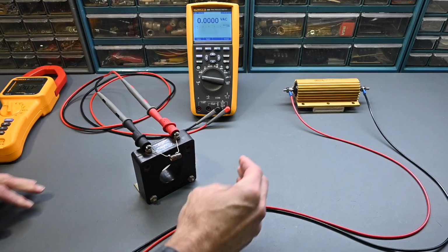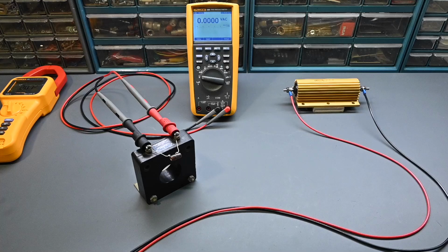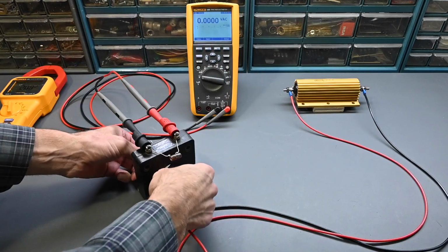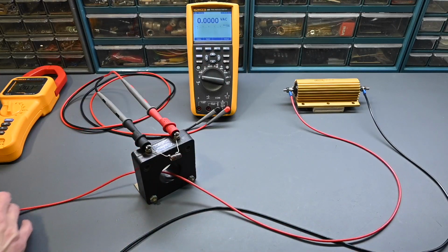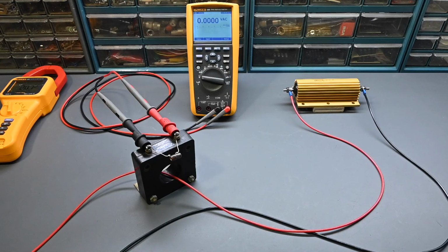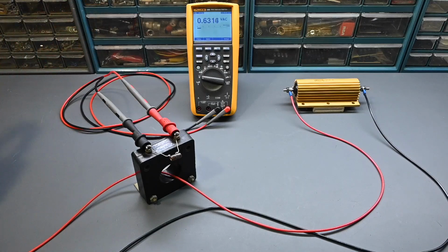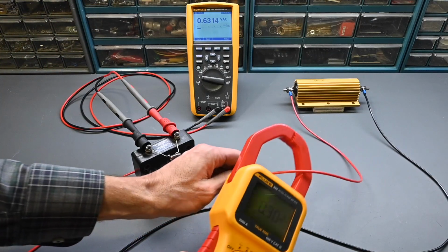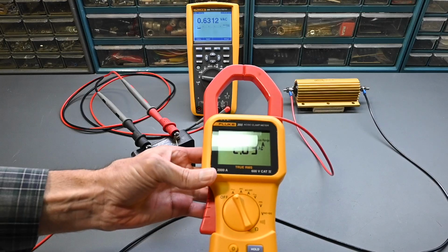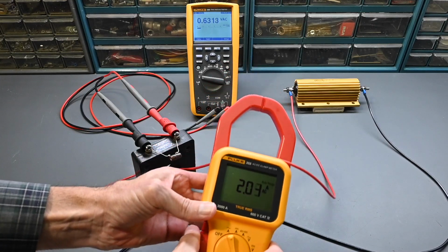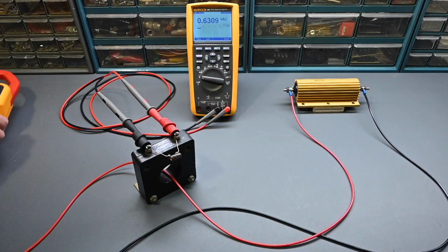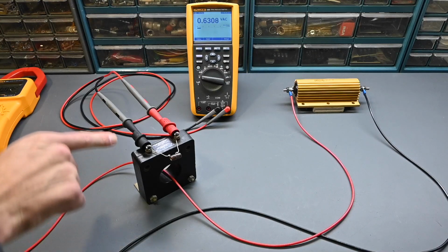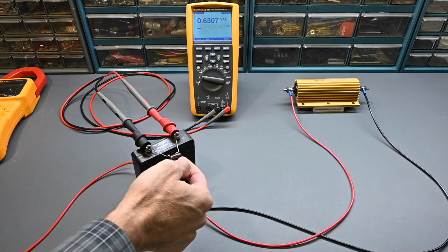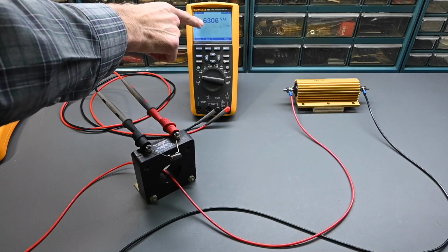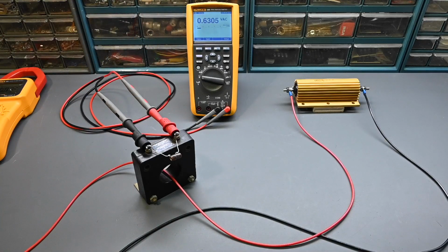All right. So this is set to volts AC. I'm going to take this wire right here, and I'll just pass it once through the transformer, and I'll connect it to the power supply. And yes, we do have a reading right there. So let's take a look. This current clamp, so you can see there is 2 amps that it's flowing. So the voltage that's being developed on the secondary with the loading of this resistor, you can see it's 0.630 and some change right there, so about 630 millivolts.